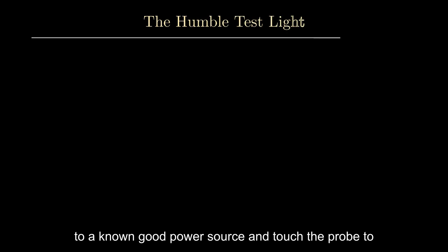A 12-volt test light offers a quicker, albeit less precise, way to check for power and ground. Connect its alligator clip to a known good ground, then touch the probe to a power source. If the light illuminates, there's power. To check for a good ground, connect the alligator clip to a known good power source and touch the probe to the suspected ground point. If the light illuminates, you have a good ground connection.